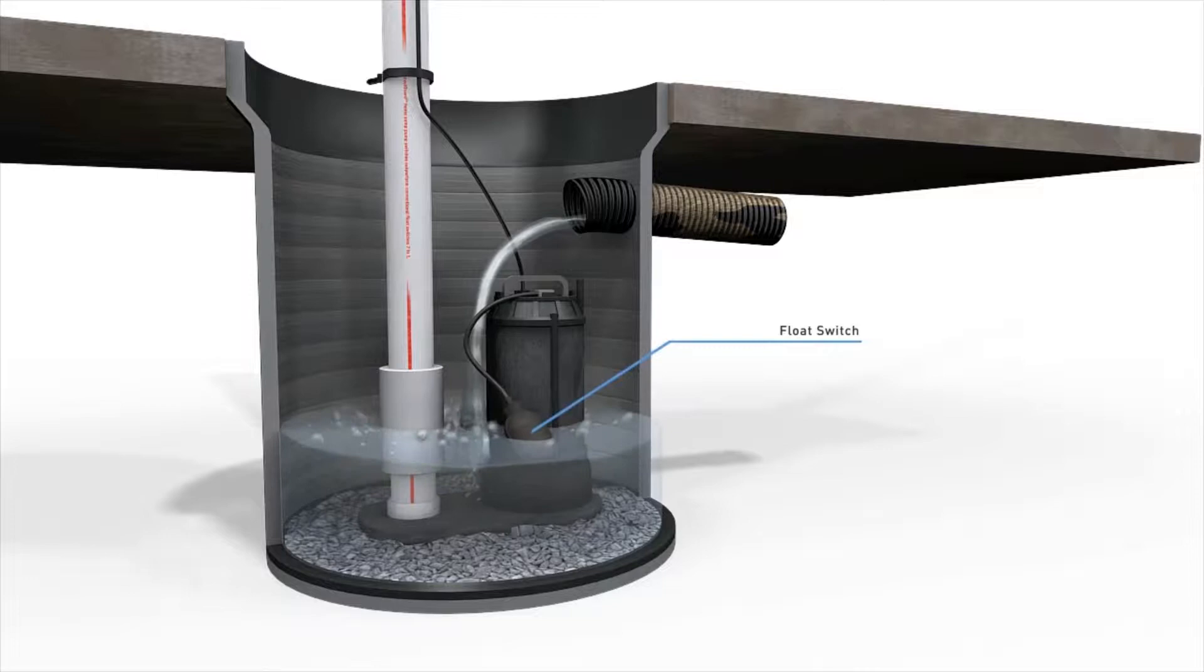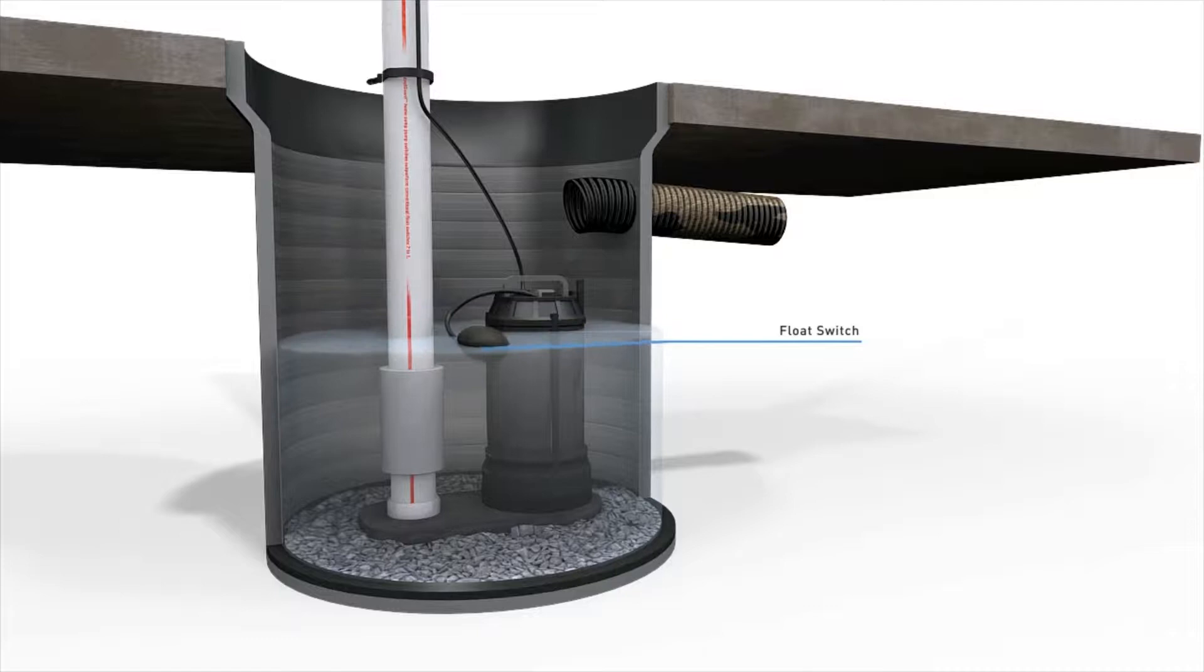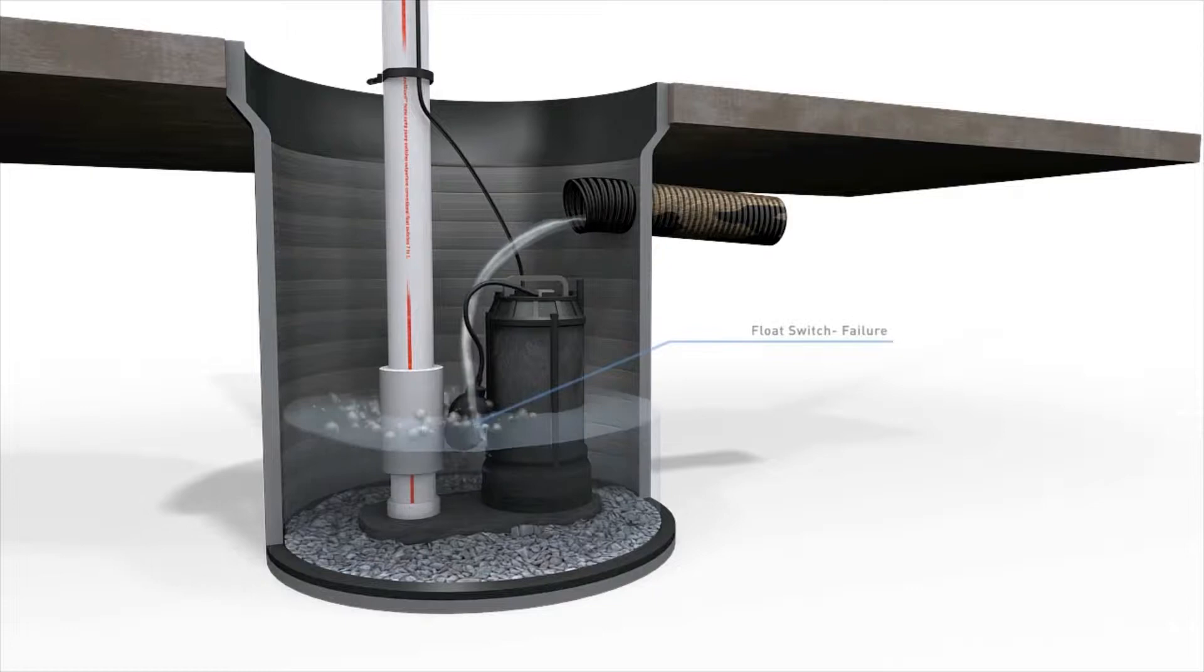Mechanical float switches activate the sump pump when they change position, typically by water filling the sump or sewage pit. They are prone to problems because they can become fouled and can fail to actuate your pump when you need it most.